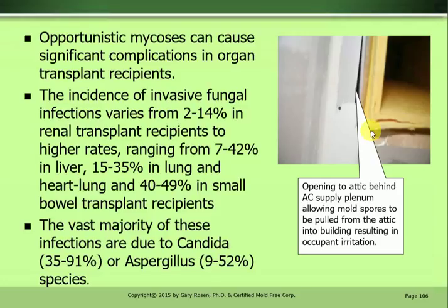And this picture right here shows opening the attic behind the AC supply plenum, allowing mold spores to be pulled from the attic into the building, resulting in occupant irritation.